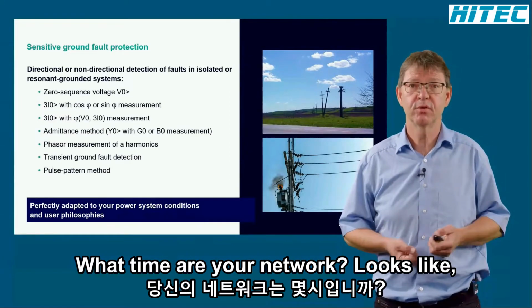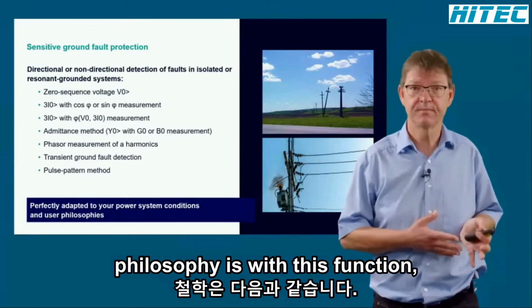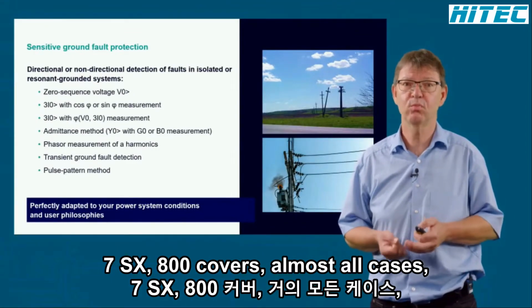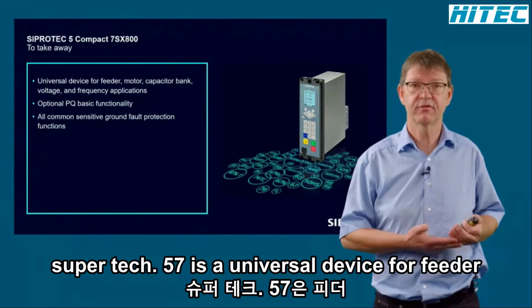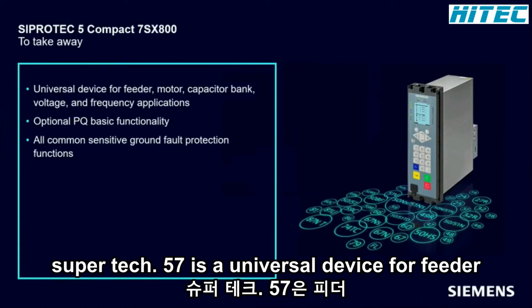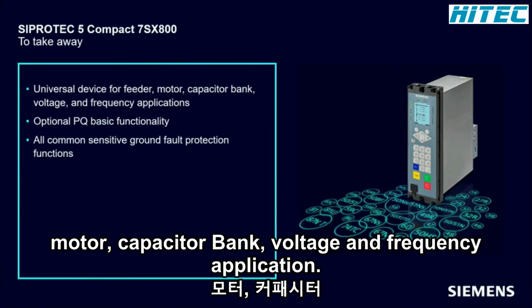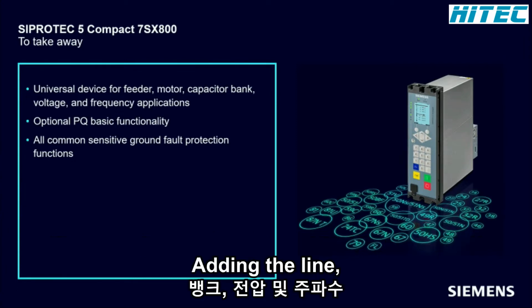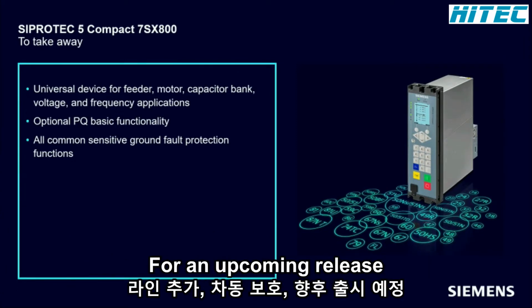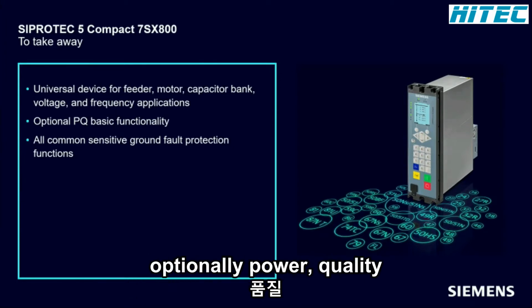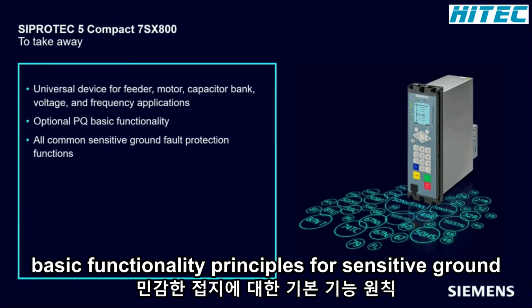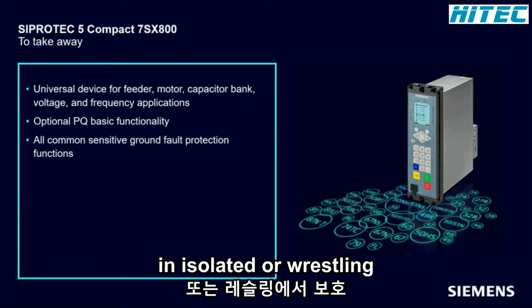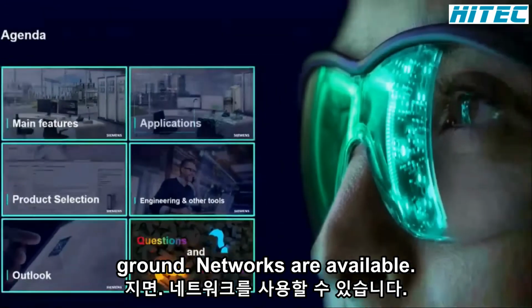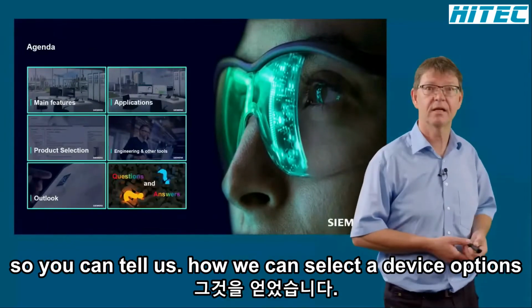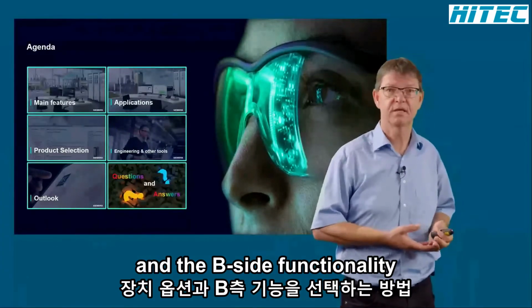To sum it up, whatever your network looks like, or how your user philosophy is, with these functions the 7SX800 covers almost all cases. To take away, the SIPROTEC 5 Compact 7SX800 is a universal device for feeder, motor, capacitor bank, voltage and frequency applications. Adding the line differential protection, expected for an upcoming release, rounds up the functional package. Optionally, power quality basic functionality can be added, and all common principles for sensitive ground fault protection in isolated or resonant grounded networks are available. Now, Yelica, you can tell us how we can select the device options and the desired functionality.